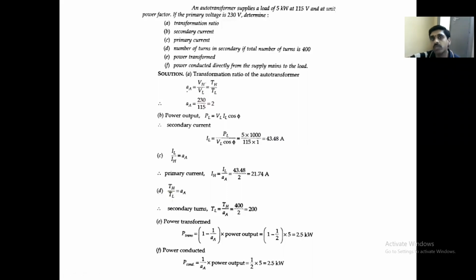So that means secondary voltage 115 means it is step down transformer. So step down transformer, here if you observe, this VH is primary, VL is secondary. So A is equal to V1 by V2. Normally we say K is equal to N2 by N1 or E2 by E1. A is equal to V1 by V2. You can take this one, A is equal to V1 by V2 for this transformer. So we are calculating that. That's why A is equal to I2 by I1. IL is nothing but I2, secondary current. IH is nothing but primary current. Okay, here high voltage is on the primary, low voltage is on the secondary. That is step down transformer.